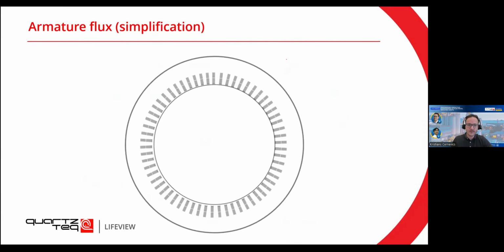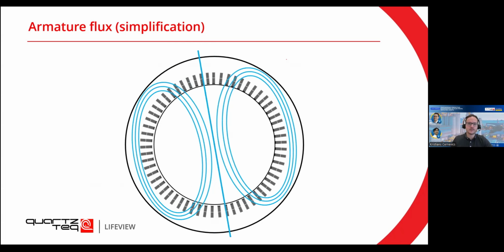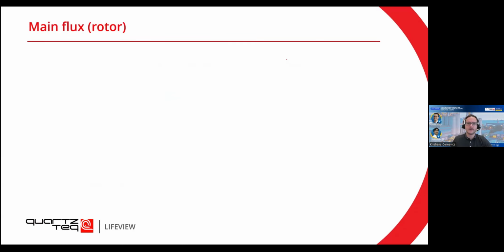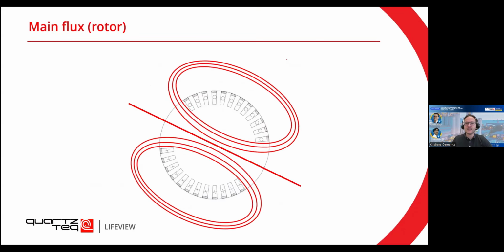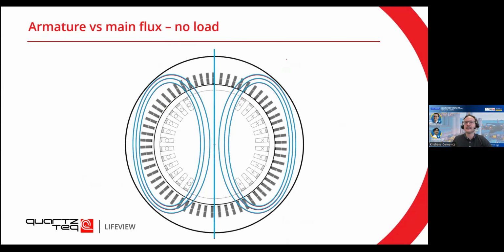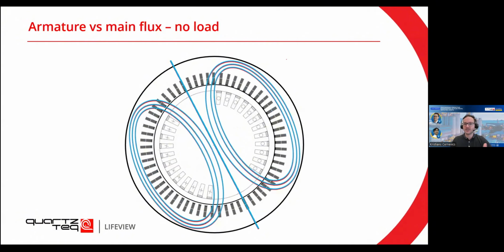So we have flux experienced from the armature, so when it turns, and then there's also the main flux from the rotor. What happens is that both of these fluxes are actually aligned when there is no load. So it's sometimes a bit hard to detect this leakage flux from your coils in the rotor, because there's also the flux from the armature. Once there is no load, these magnetic fields are nearly aligned. There's no difference between them. However, this is rotating, and then it's a bit harder to get the data.